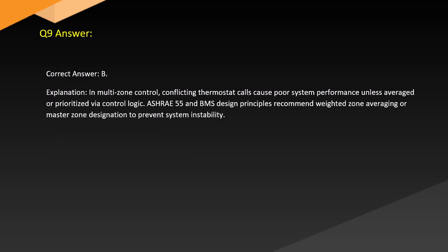Answer. Correct answer: B. Explanation. In multi-zone control, conflicting thermostat calls cause poor system performance unless averaged or prioritized via control logic. ASHRAE 55 and BMS design principles recommend weighted zone averaging or master zone designation to prevent system instability.